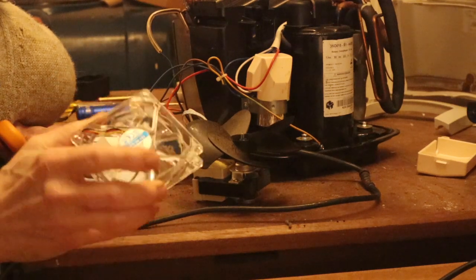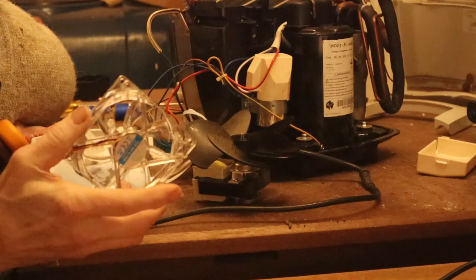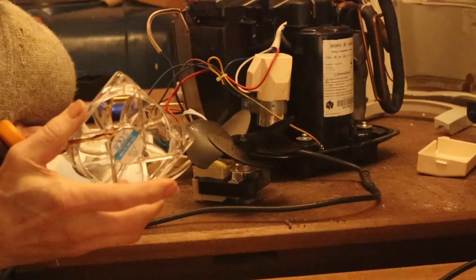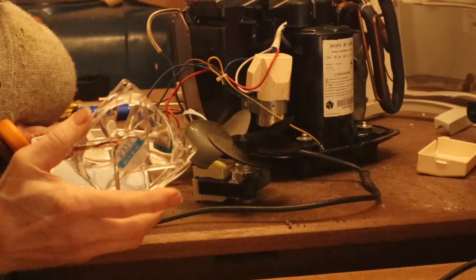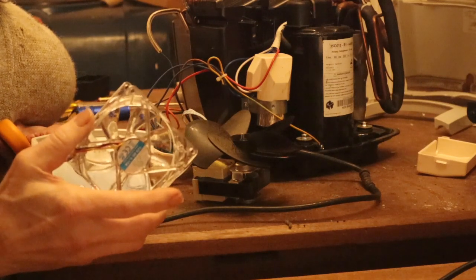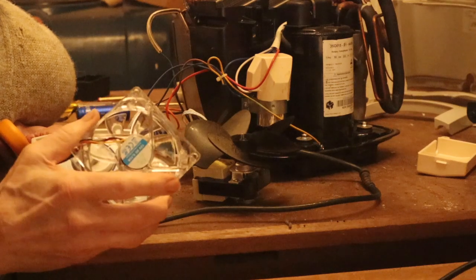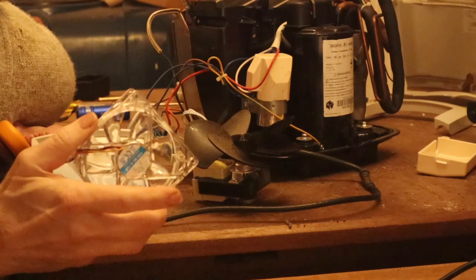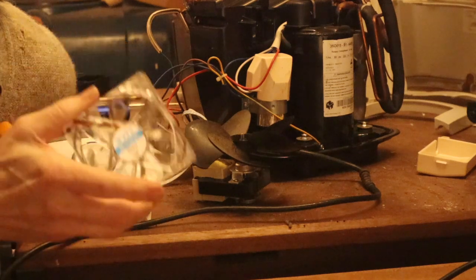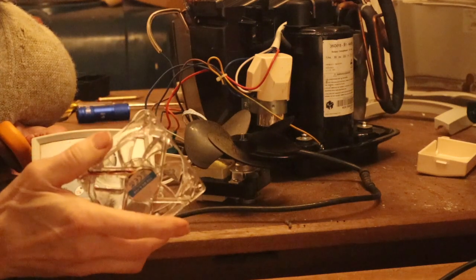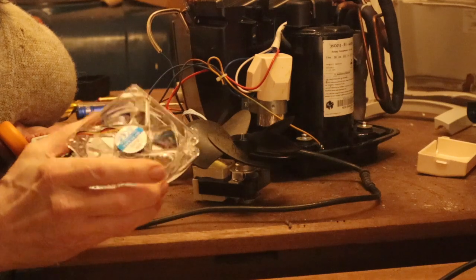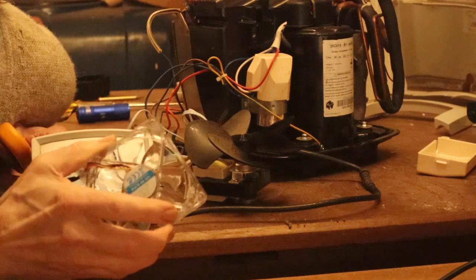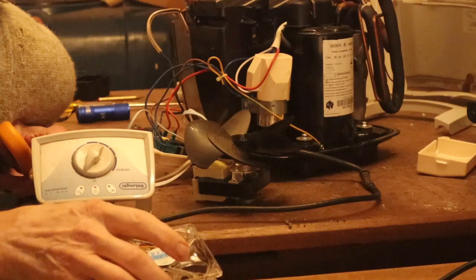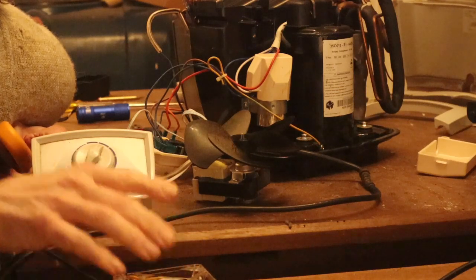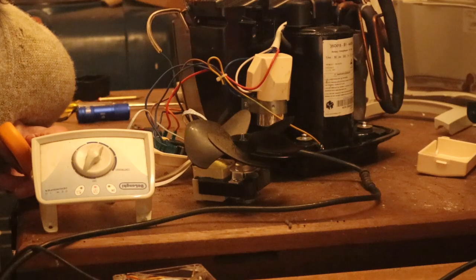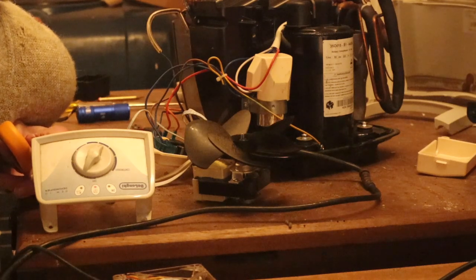But then you haven't calculated the resistance of the evaporator and the condenser, because the air must go through those metal grills, and that will then be a little bit less, let's say maybe 20 cubic meters per hour, just with this fan. Well, we have to measure that, because if that doesn't go well, then we have to use the restroom fans, those fans which you always see in the restroom, and which are switched on together with the light. Those are much stronger.